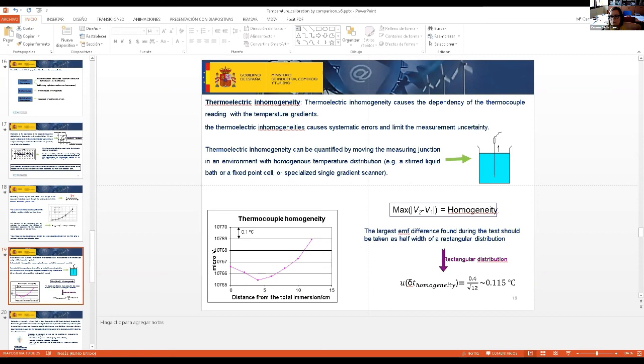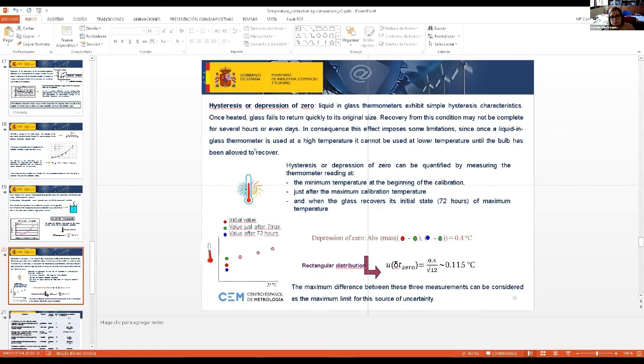The thermocouple homogeneity: the wires in a thermocouple are not homogeneous, and the electrons running inside these wires don't run as freely as we think in theory, and this has influence on the relation between the final difference of voltage and the temperature. And the hysteresis or depression of zero in liquid in glass thermometers is the same as in resistance thermometers. It means that the liquid doesn't recover in the same way as the glass when the change between very high temperature and very low temperature is fast.